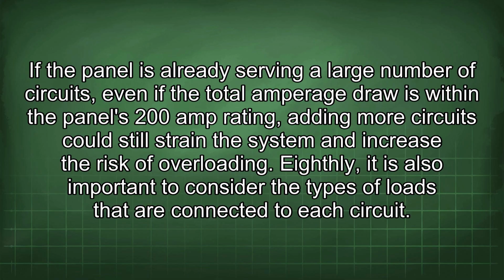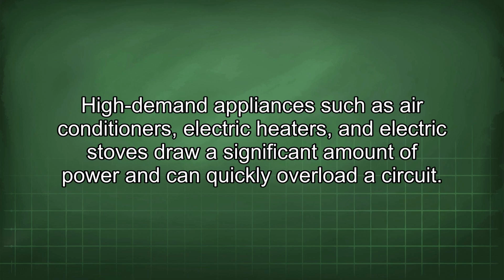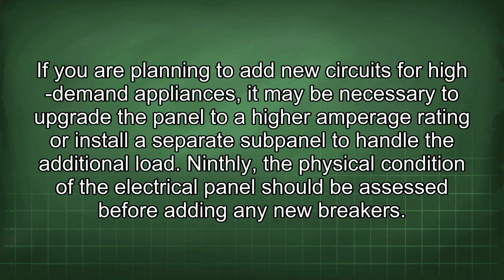Eighthly, it is also important to consider the types of loads that are connected to each circuit. High-demand appliances such as air conditioners, electric heaters, and electric stoves draw a significant amount of power and can quickly overload a circuit. If you are planning to add new circuits for high-demand appliances, it may be necessary to upgrade the panel to a higher amperage rating or install a separate subpanel to handle the additional load.